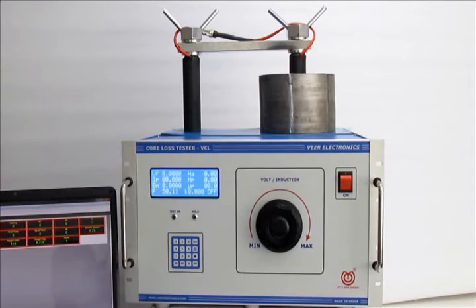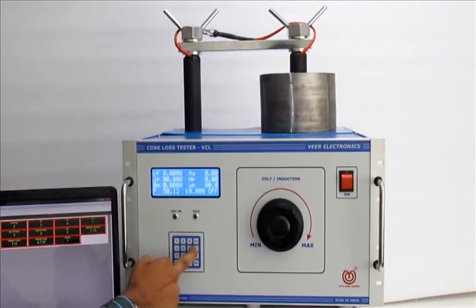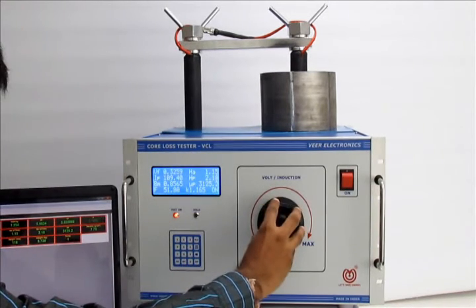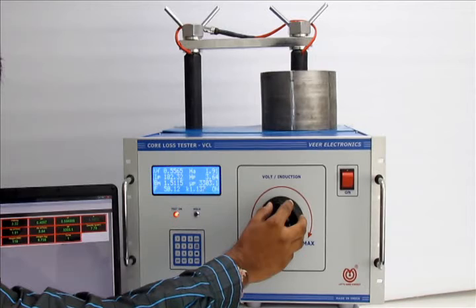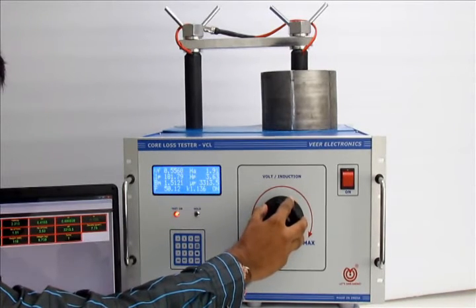Now I am pressing this on-off key to turn on the test. Now I am setting flux density as 1.5 Tesla induction using this flux voltage setting knob.